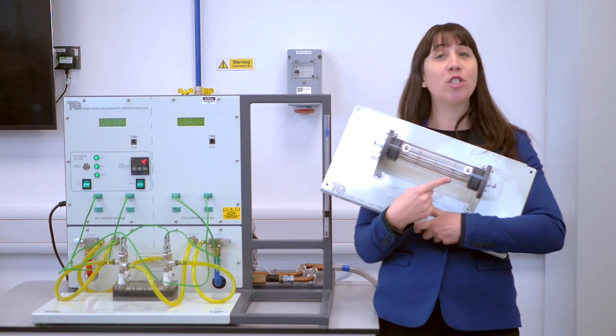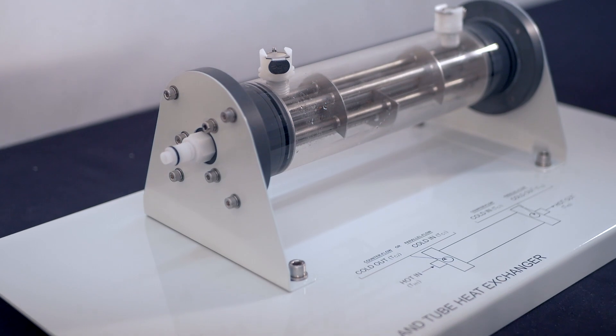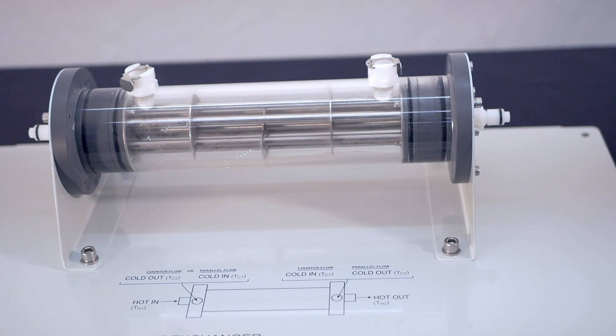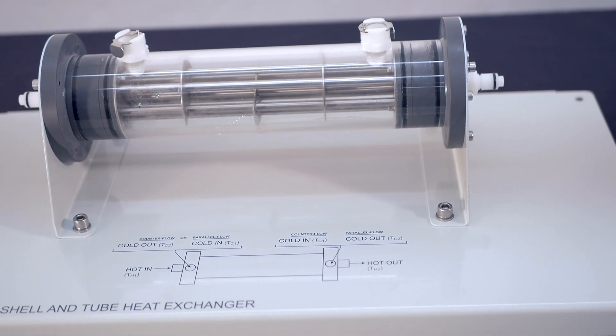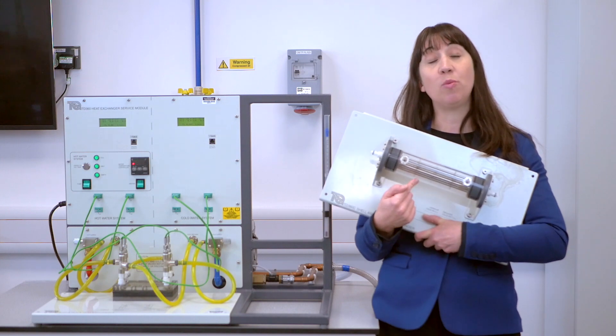It's around several smaller tubes. These are referred to as a bundle. One water circuit passes through the bundle and another through the shell, with heat transferring between them. The bundle itself has baffles to help create a turbulent flow to mix up the water within the shell.